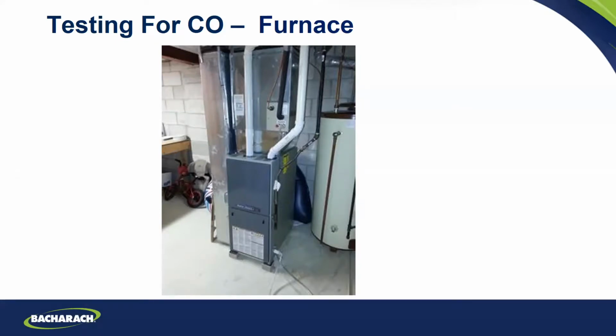So you go down and look at this furnace, and there's about 10 reasons why the furnace may be making carbon monoxide. So you want to test it, as we showed you where to test before. You can have too high a gas pressure or too low a gas pressure, so you definitely want to set your gas pressure. You can have too high a draft or too low a draft. If it's too low a draft, those gases back up and they burn fuel rich.